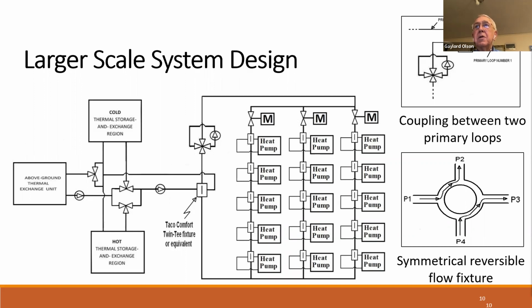So if you analyze this, what you'll find is if you have the same flow rate in 2 different nearby primary loops, you will end up with the flow going through both primary loops before it gets back to the starting point. In other words, if you try to follow a molecule of water starting in primary loop number 1, that molecule is going to have to flow all the way through primary loop number 2 and then come back and flow back to where it started in primary loop number 1. What that means is any large heat source or large cold source in any of those heat pumps or chillers is going to be shared with everybody else in both primary loops, not only one. What we did not show here is the need for isolation valves.